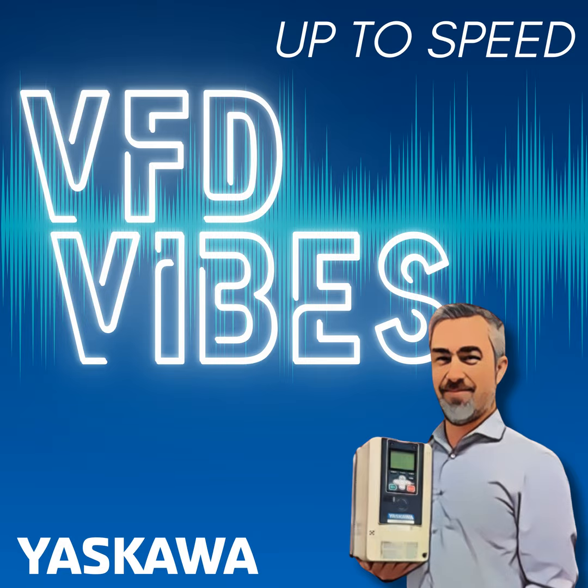We talk about the three wires. These three wires come from the secondary of this three-phase transformer, which converts the medium voltage down to the distribution voltage within the facility. The most common connection is to have three 277-volt windings connected in a Y configuration so that one end of each winding becomes the phase voltage, A, B, or C, and the other ends are all connected together at the center of the Y, and these become the neutral point. Now you say, well, that's 277 volts. That's because 277 is 480 volts divided by the square root of 3.